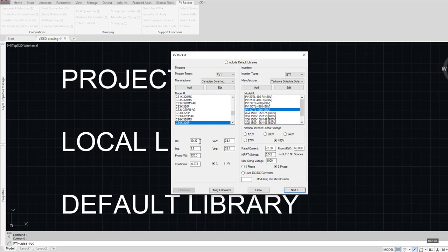all separate is, like on the inverter side, a coming thing is the rated current is changing from one project to the next. Even though the cut sheet is the same, they'll both be Chint Solectria PVI 60 TLs, but you'll have, well, that's funny, that's the one that I've got right here, Solectria PVI 60 TL. One will have the rated current at 72.3 and the next one will have 75.6 or something. Why is that coming? Even though they're the same cut sheet and the same model?